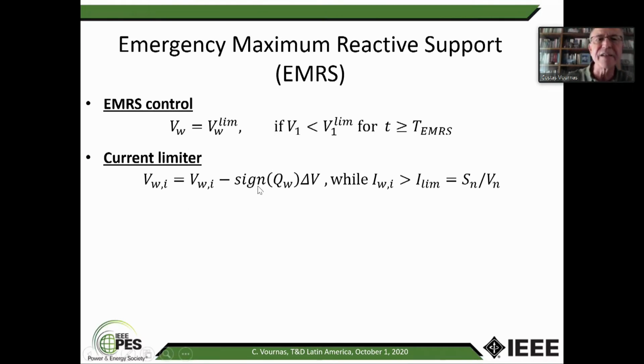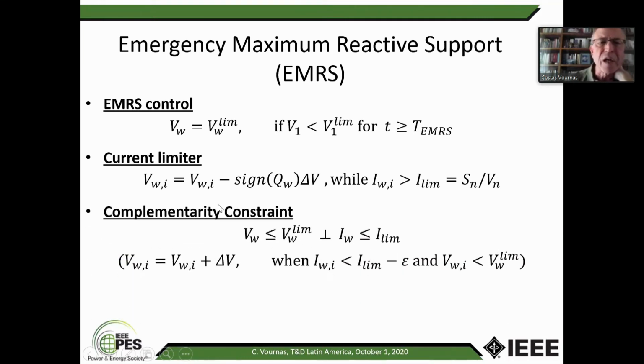The sign here is because you may have a case where your wind farm is absorbing reactive power. So in this case, if you absorb too much reactive power and you go to the limit, you have to increase your voltage. But in the case we are considering here, because we are providing reactive support, the only thing we can do is lower the voltage.